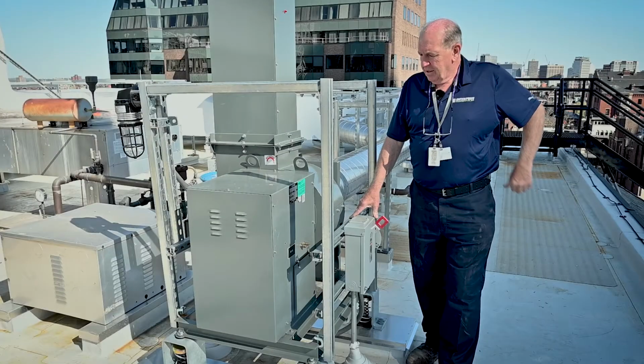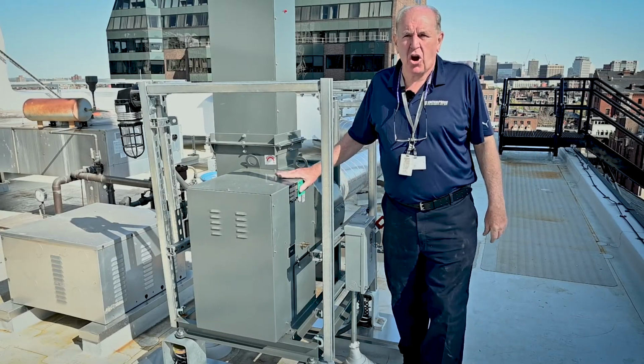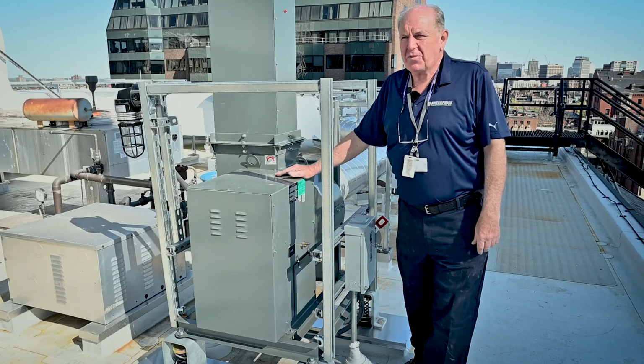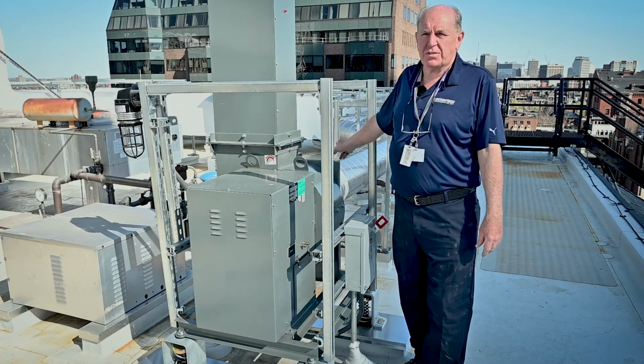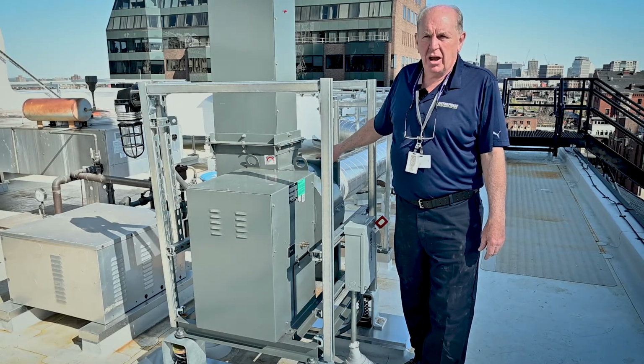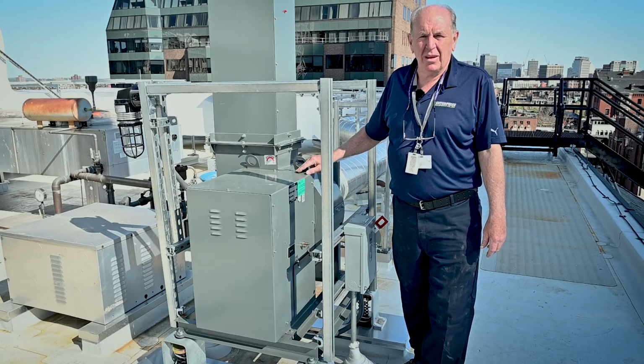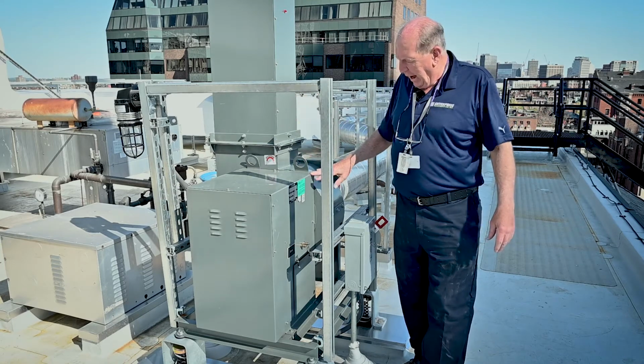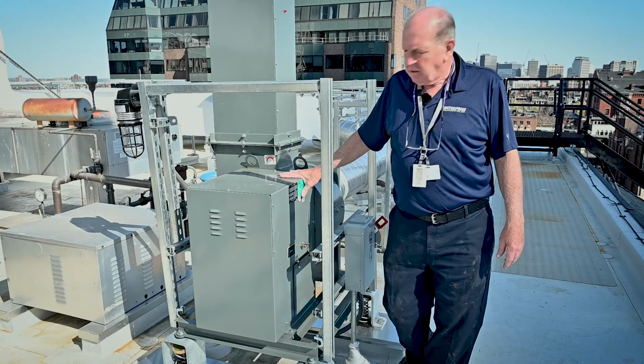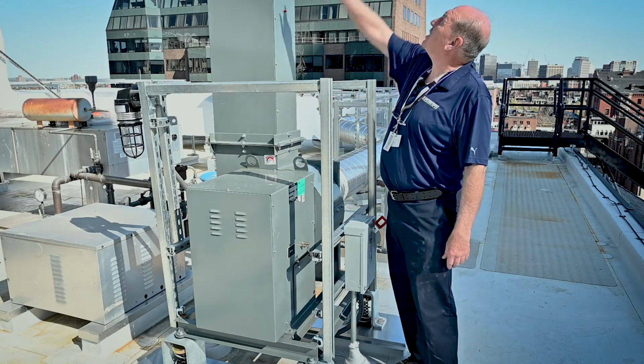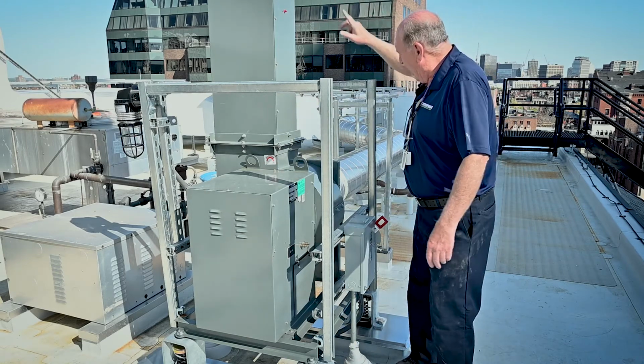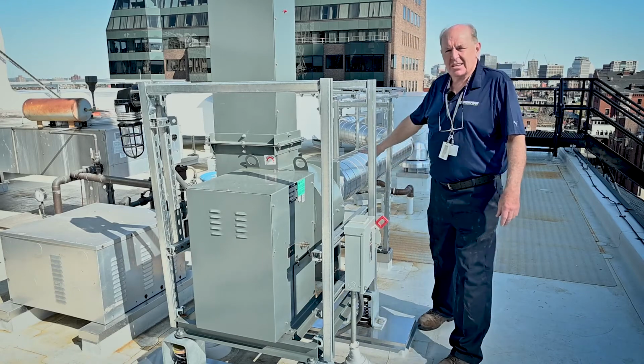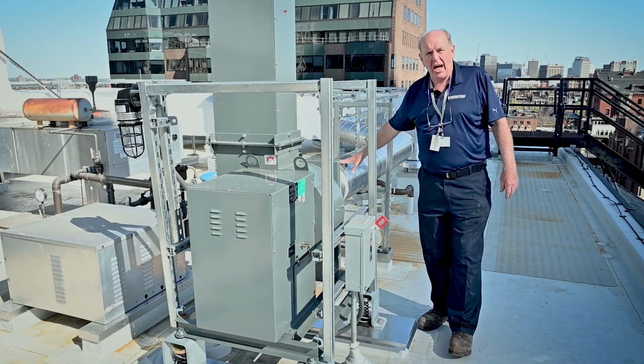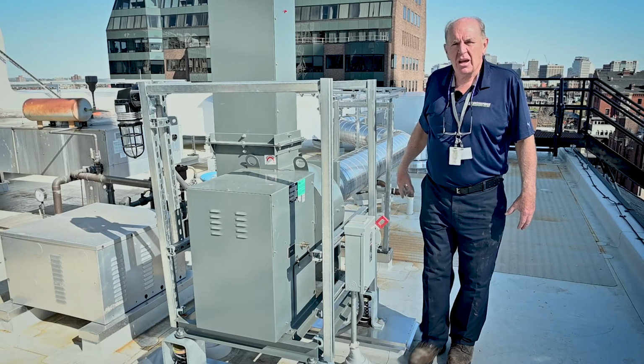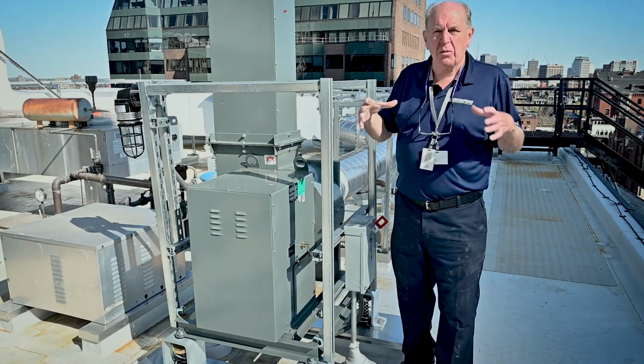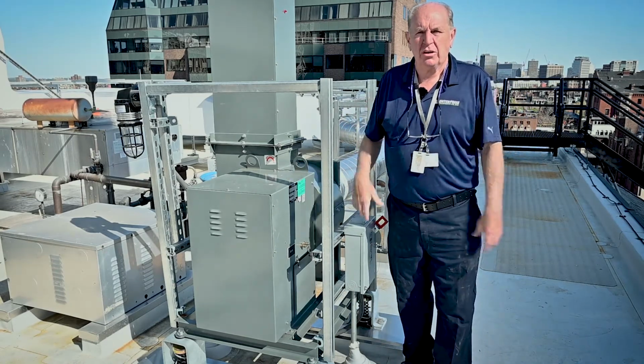Okay. This is exhaust fan 3, feeds the conservation lab. It's fed by 2 EVAVs, 2 exhaust VAVs. One's a fume hood, and one is just a general lab. It's a 1/2 horse belt-driven exhaust fan. Just discharges straight up. It's all stainless steel ductwork coming from the lab, and inside the building, it's all insulated with fireproof insulation.